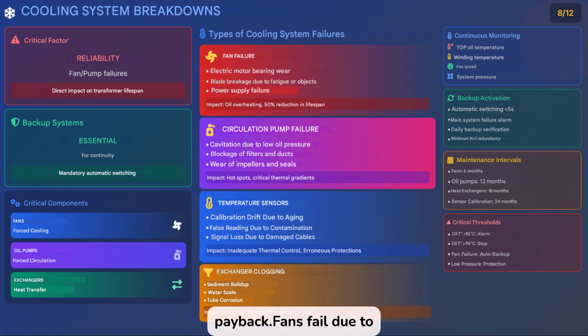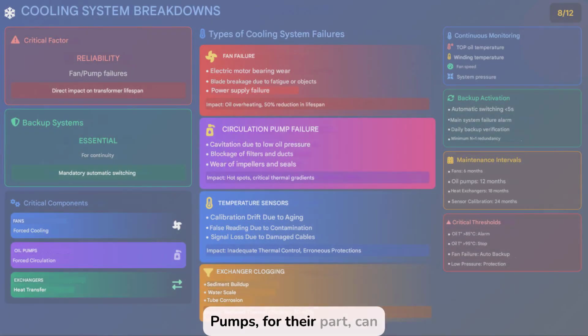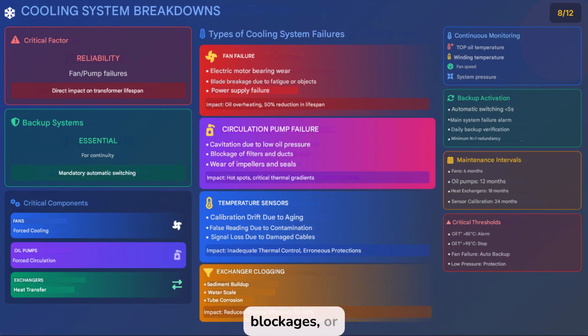Fans fail due to mechanical wear or electrical faults, which reduces heat dissipation and degrades the dielectric oil. Pumps, for their part, can experience cavitation, blockages, or wear, creating hot spots that damage insulating materials. Temperature sensors, if miscalibrated or contaminated, produce erroneous readings that prevent adequate protection. Heat exchangers are also critical. The accumulation of sediment or corrosion can reduce their efficiency by up to 60%, forcing the system to operate at higher temperatures, which accelerates the wear of all components.